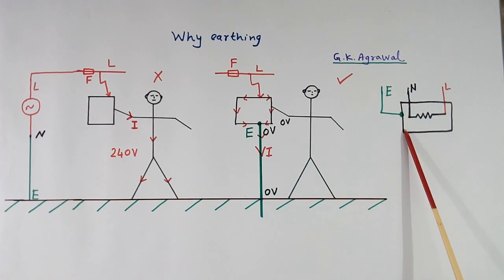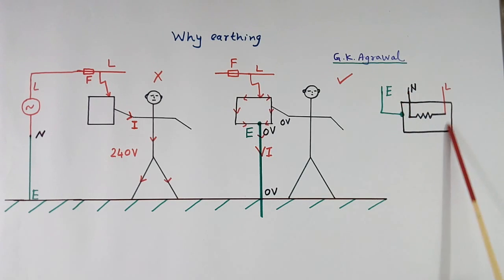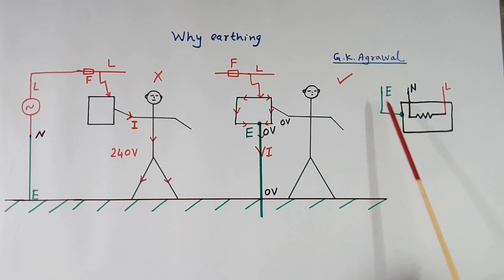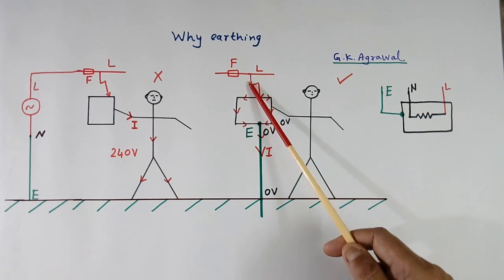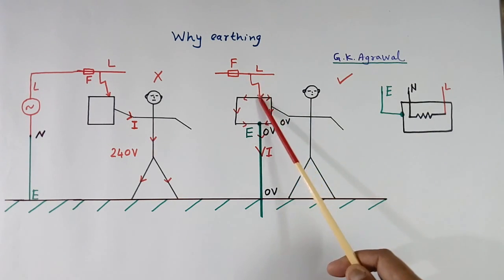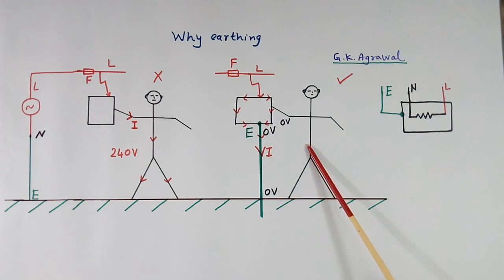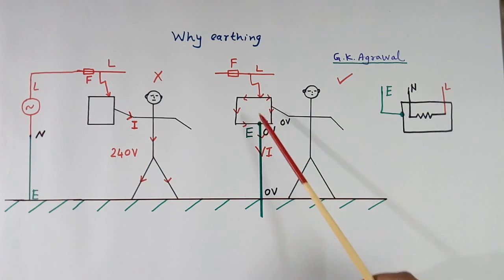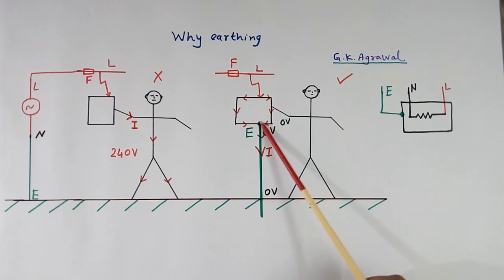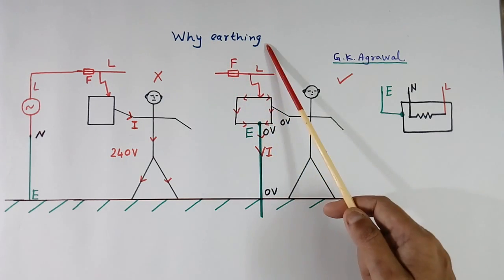Now here the same equipment is shown, but the load is connected across line and neutral, and the body is connected to earth and is grounded. If a fault comes, then current will flow through the earth path — no current will go through our body. So we will be safe, there will not be any shock, and this voltage will be zero. Because of shorting, heavy current will flow, so the fuse will also blow. The main purpose of earthing is safety.